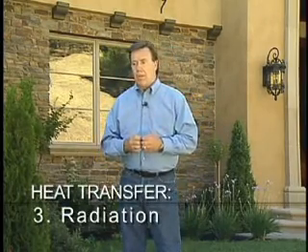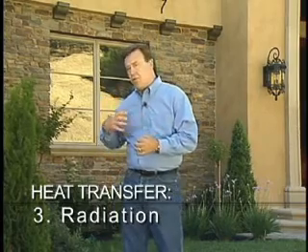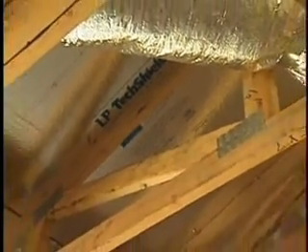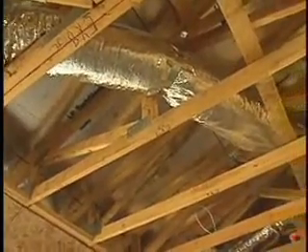Another factor of heat transfer is called radiation. Radiation heat transfer happens like your warmer body wants to radiate heat to a colder surface. Or for example, if you're staying in the shade and you step into the sun, you immediately feel that radiant energy from the sun. Now we use low emissivity glass that's basically heat reflective to reject or reflect some of that heat from the sun. Or we use radiant barriers in our roofs so that the heat energy from the sun does not get re-radiated into the building envelope. That's how we control heat transfer by radiation.